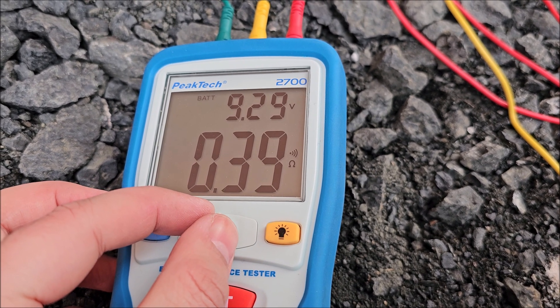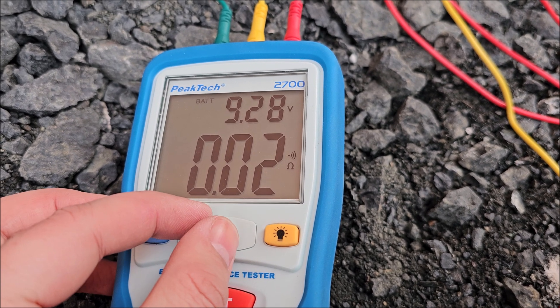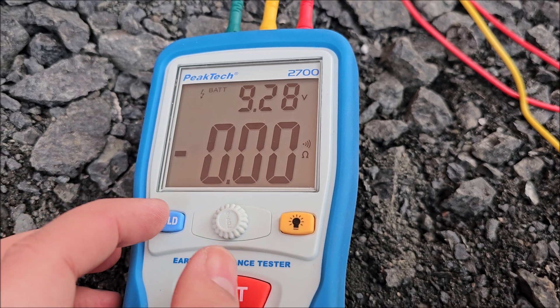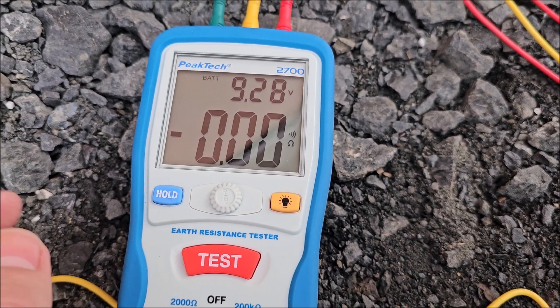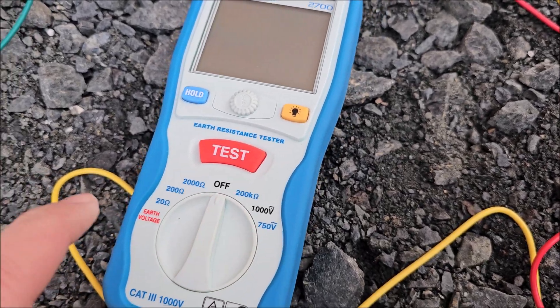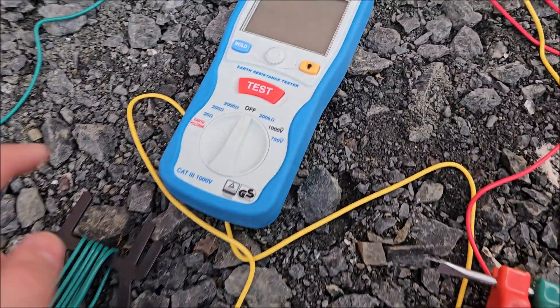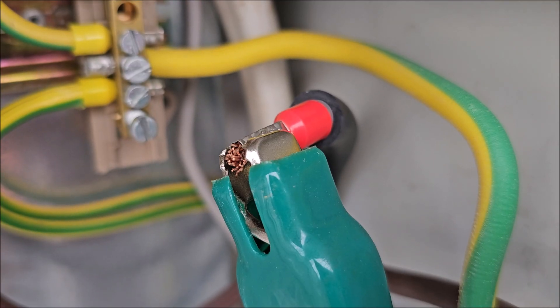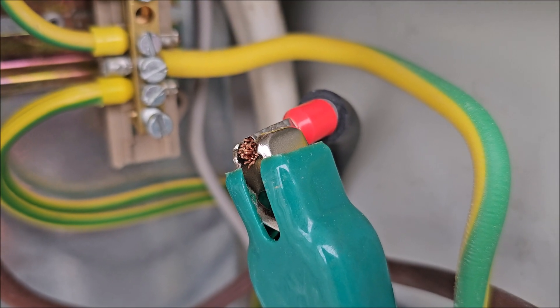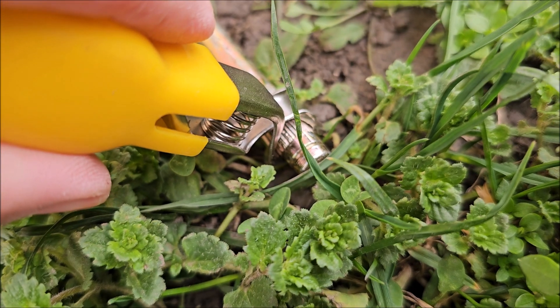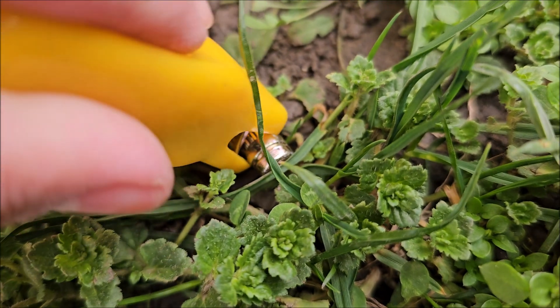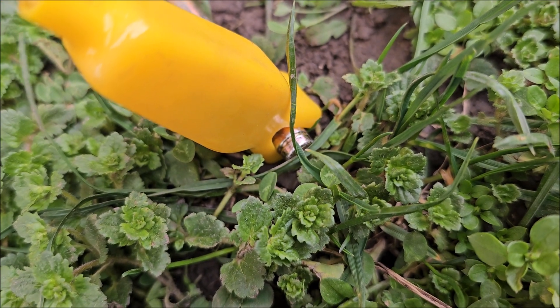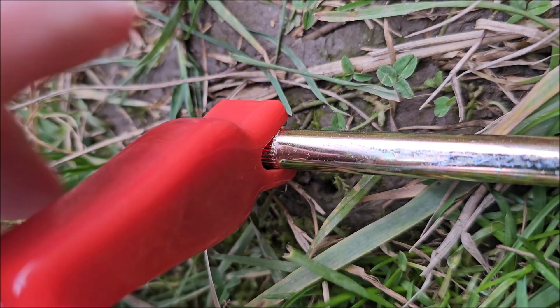So we want to be on zero so the wires themselves don't matter at all, and it's perfect. So now I go to off and then connect everything in place, and then we will do the earth voltage test first. Clamp is connected, now I'm going to connect the second yellow one and third red one. Connected third clamp, and now we are ready for measurement.